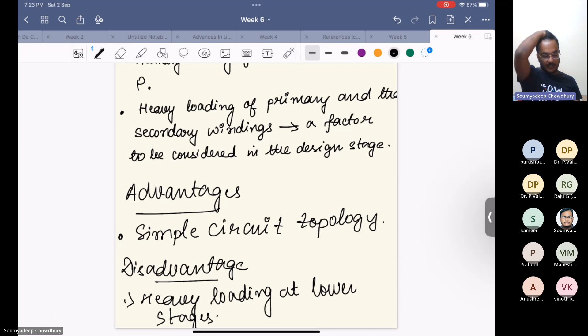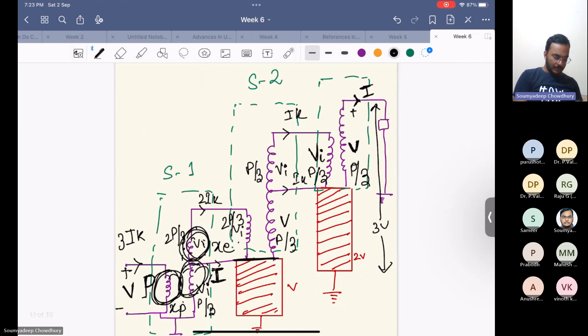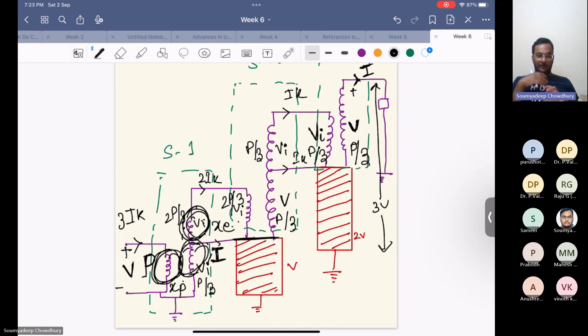At the lower stages, this is one disadvantage. The first disadvantage is the heavy loading at the lower stages of the transformer, because the power rating of the stage 3 transformer is only P by 3, whereas the total power rating of the primary of the first transformer is P, that is 3 times. So at lower stages, if you have 7 or 10 stages, there will be a difference of power of at least 7 to 10 times. So heavy loading is present at the lower stages, and that is a factor to be considered in the design stage. That is one disadvantage.